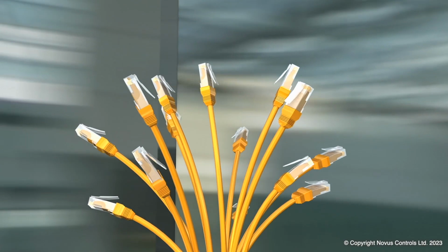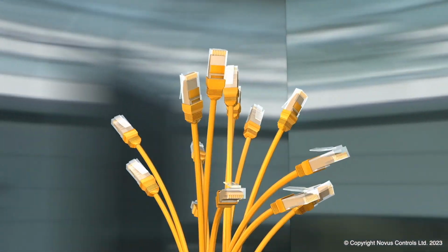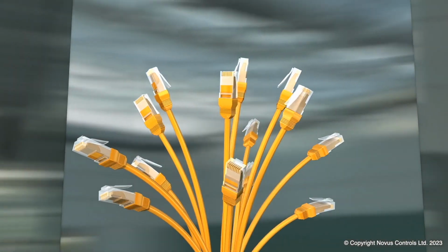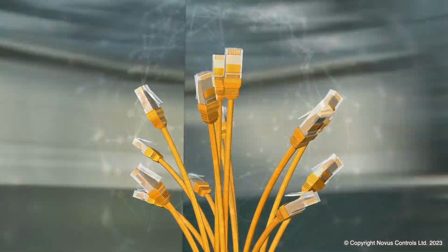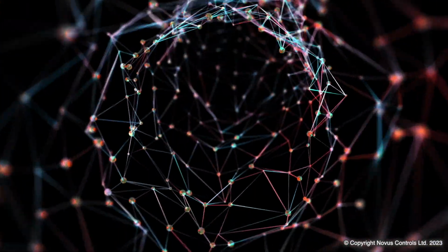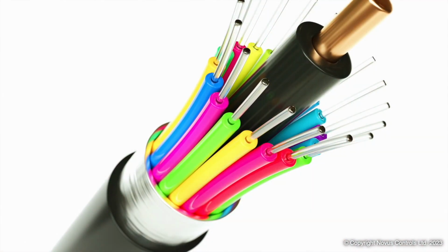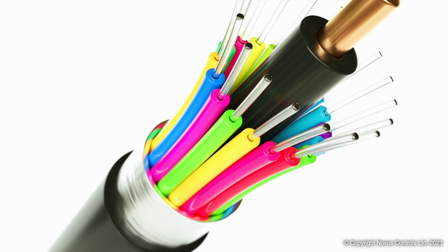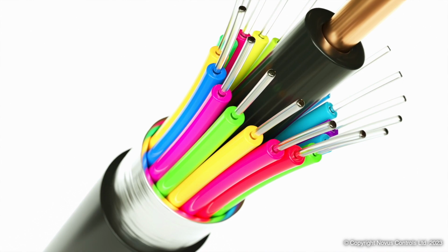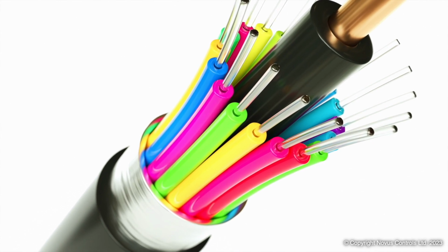With copper cables, however, you need one full cable for each link. A good comparison here is to consider 24 links between two data cabinets. This would require 24 individual Cat6 cables, but the same can be achieved with a single 48-core fibre cable. A typical 48-core fibre cable for internal use is about the same size as one Cat6 cable.